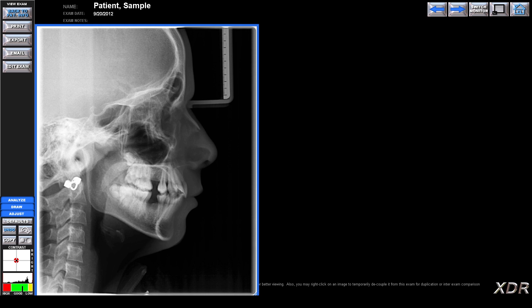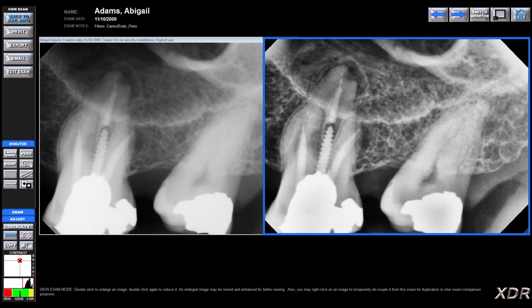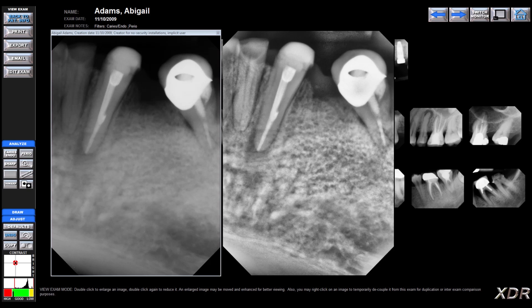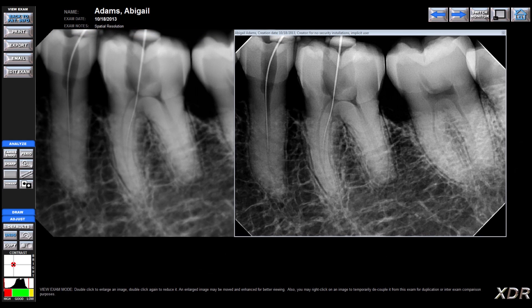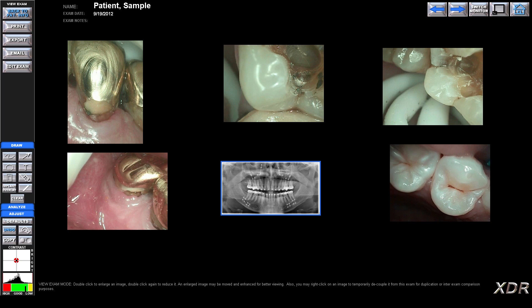And then with the software, what I've found to be interesting is that you have these algorithms — I'll call them filters — where you can see caries differently, or endo differently, or perio differently. One of the neat things about digital sensors is that they have sensitivities to grayscale that go beyond that of the human eye. But if you just present it verbatim on the screen, it really doesn't pop. As image processors, we're able to accentuate that additional sensitivity by stretching out the histogram in that part of the grayscale so that the human visual perceptual system can see these things better. So you can zoom in on brightness for caries in one mode and zoom in on endo or perio lesions in another mode — not in a spatial sense, but in brightness.